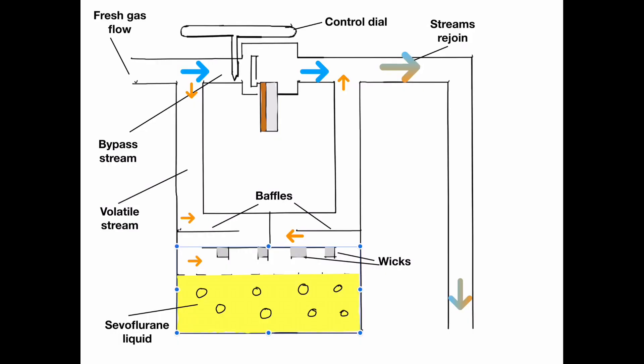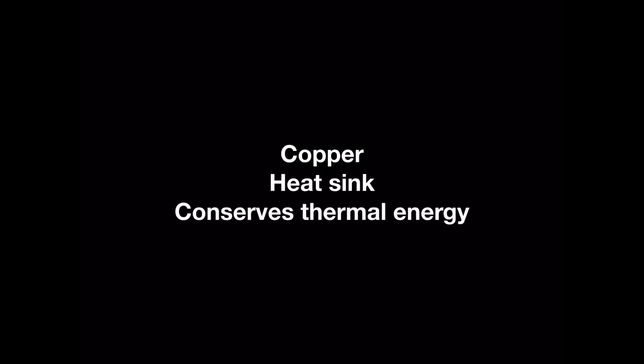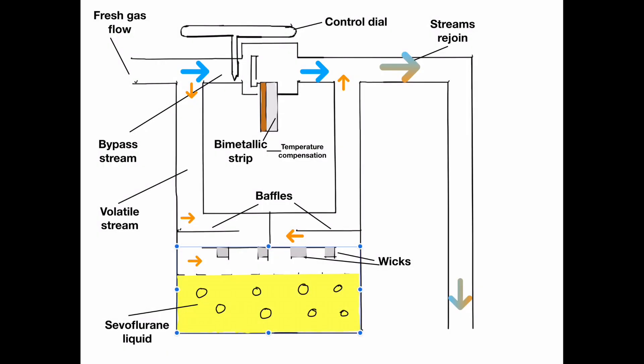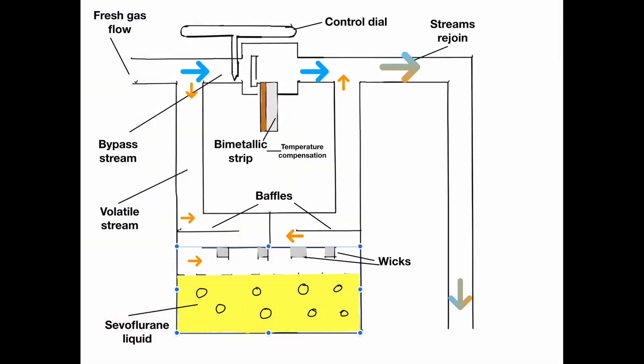To combat this, the vaporizer needs to have methods of temperature compensation. Modern vaporizers are made of copper, which is a good heat conductor and, because of its high mass, it acts as a heatsink to keep the thermal energy within the system. The other mechanism present is the bimetallic strip. This is a strip of two metals which expand at different rates as they are heated, usually made of steel and copper. The different expansions force the bimetallic strip to bend one way if heated or the other if cooled. This principle can be utilized to increase or reduce the amount to which the volatile stream is diluted by the bypass stream, and therefore the overall concentration of the volatile delivered.